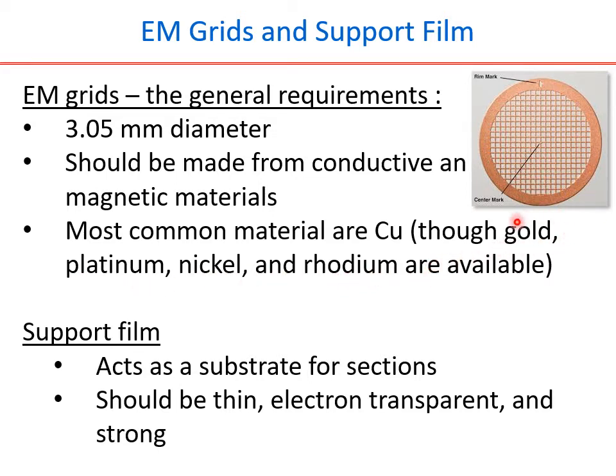The gold, and especially the nickel, will be used in specific cases where you will be going for what is called gold immunolabeling. It is known that sometimes the gold may interact with the copper, and that's why we don't want any specific interaction between the immunogold and the copper. In that case, people prefer to use nickel grids. So as I said, for most general applications, a copper grid is sufficient, but for specific applications, if your sample demands, there are other options available where you can go for gold, platinum, nickel and rhodium.